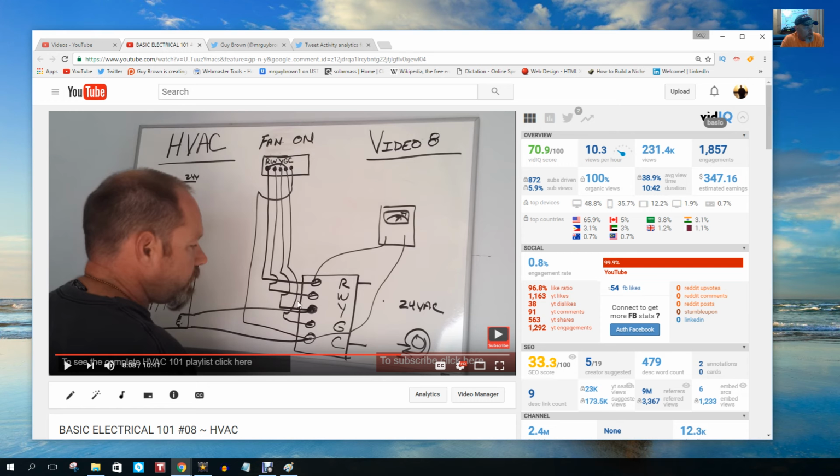So the furnace here, and the thermostat here, and this over here under my chin is the condenser, or the outdoor unit. So power comes in on the R and the C from the furnace, from the furnace's transformer, 24 volts. C is common, and R is our hot wire.